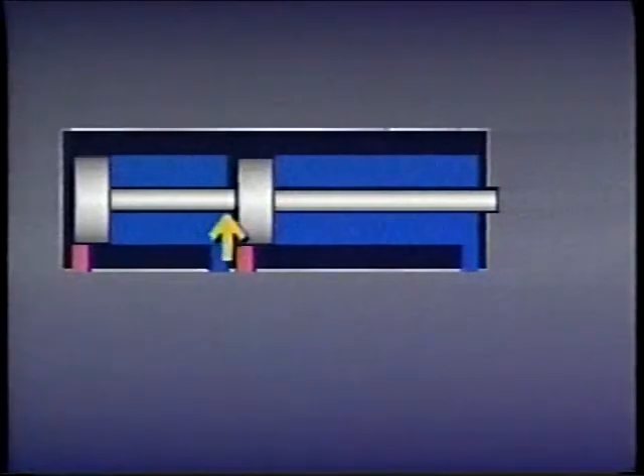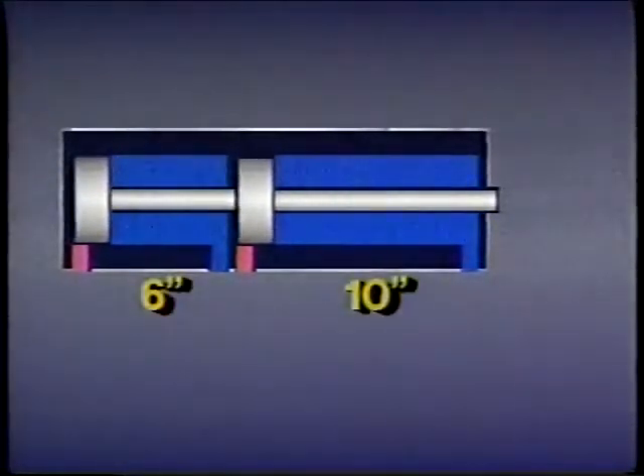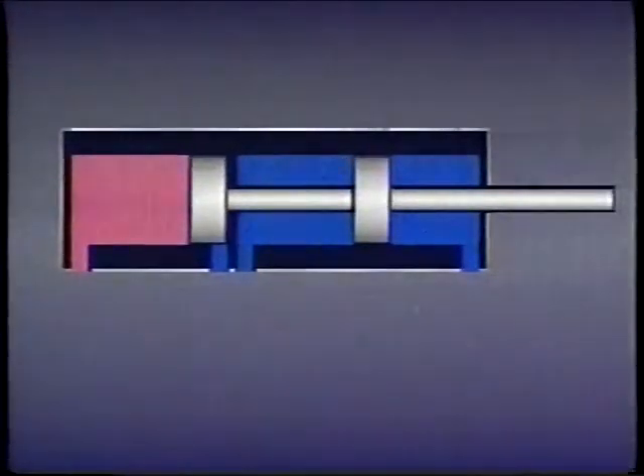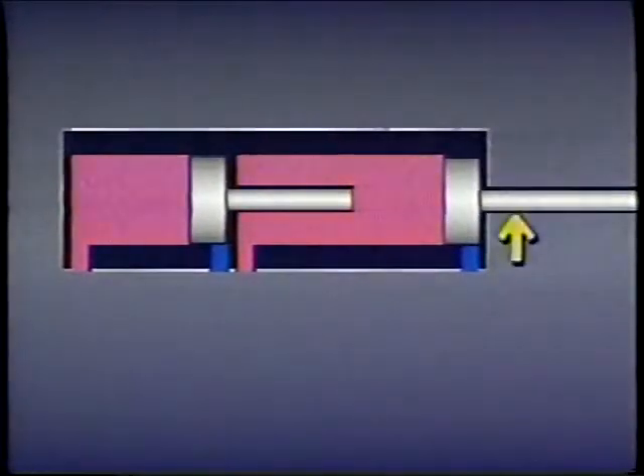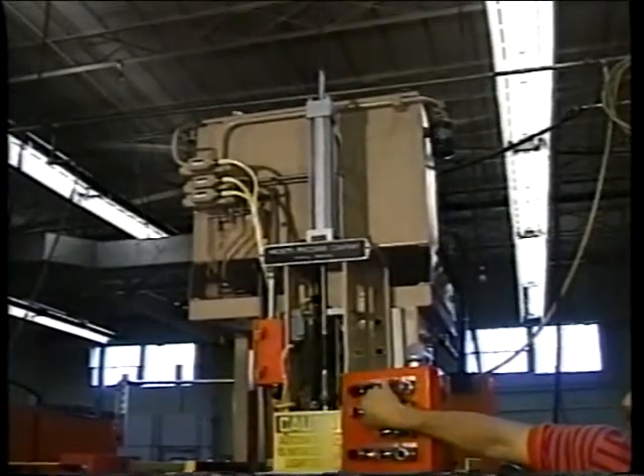Unlike tandem cylinders where the pistons are joined to the same rod, the rods in a duplex cylinder are not connected — each rod has a different stroke. This allows the load to be moved to several positions. For example, a duplex cylinder with strokes of six inches and ten inches can move loads to one position when both pistons are at one end, to another position when the six-inch stroke is extended, and to a third position when the ten-inch stroke is extended.